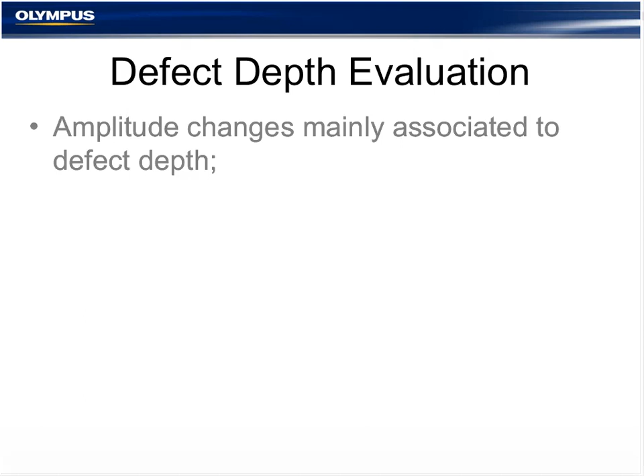One interesting aspect of eddy current array is its ability to evaluate defect depth. One of the first factors influencing the amplitude changes is the depth of a defect, and I'm speaking of a surface breaking defect. The amplitude translates to colors in the C-scan. Therefore, the color is a representation of the depth when calibrated properly. So it's possible to set up the instrument easily to display different colors for different depths. Eddy current array, like conventional eddy current technology, will provide valuable information on flaw depth within, of course, the limits of eddy current capabilities.